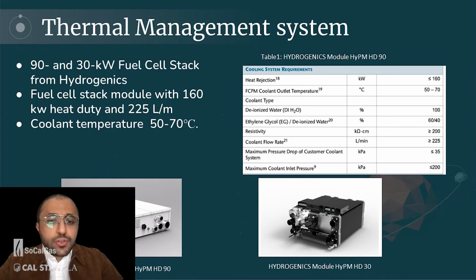The purpose of the thermal management system in this project is to design a cooling system for the fuel cell stack in the backup powered system to reject sufficient heat. I chose a 90 and a 30 kilowatt fuel cell stack from Hydrogenics to design the cooling system. The requirement for the cooling system for the 90 kilowatt model is 160 kilowatt heat rejection, and for the 30 kilowatt model, we need 30 kilowatt heat rejection. For both models, we need a cooling temperature between 50 to 70 degrees Celsius.